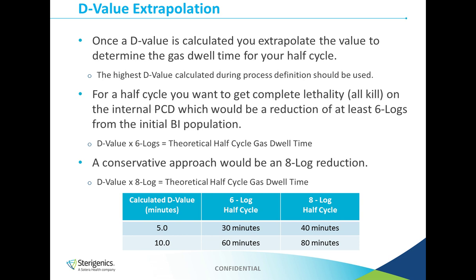Now, when you're determining what time to use for your half cycle run, you need to take into consideration that external PCD. Yes, that internal PCD is what you base lethality off of, but you also want to make sure that you look at the D value for your external and make sure it falls within that range so that when you move forward with the half cycle, you can get the appropriate kill that you need, and then when you move forward with the full cycle, you can get all the kill that you need.